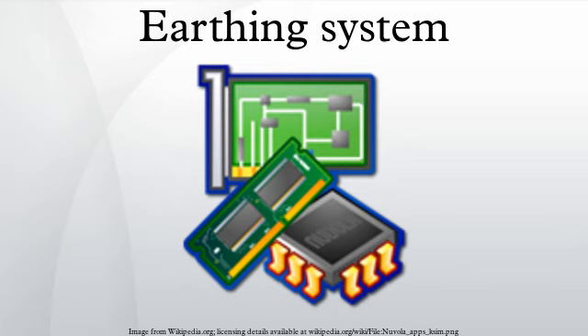Live and neutral might be accidentally reversed in the outlet or plug, or the neutral to earth connection might fail or be improperly installed. Even normal load currents in the neutral might generate hazardous voltage drops. For these reasons, most countries have now mandated dedicated protective earth connections that are now almost universal. If the fault path between accidentally energized objects and the supply connection has low impedance, the fault current will be so large that the circuit overcurrent protection device will open to clear the ground fault. Where the earthing system does not provide a low-impedance metallic conductor between equipment enclosures and supply return, fault currents are smaller, and will not necessarily operate the overcurrent protection device. In such a case a residual current detector is installed to detect the current leaking to ground and interrupt the circuit.